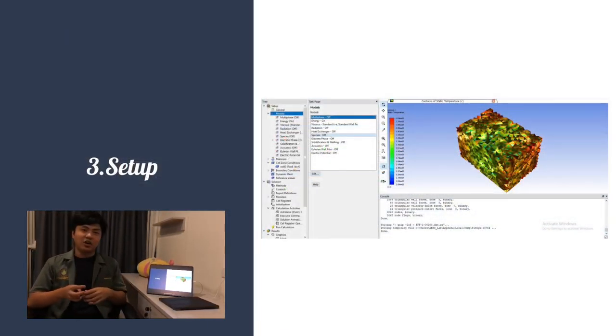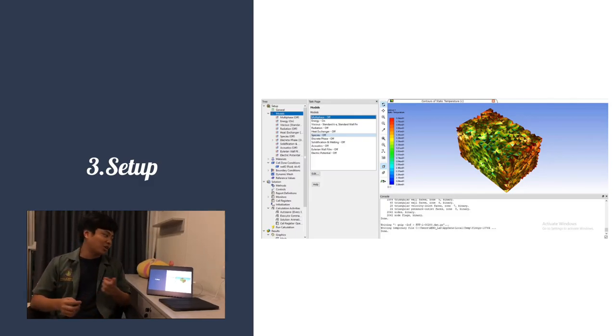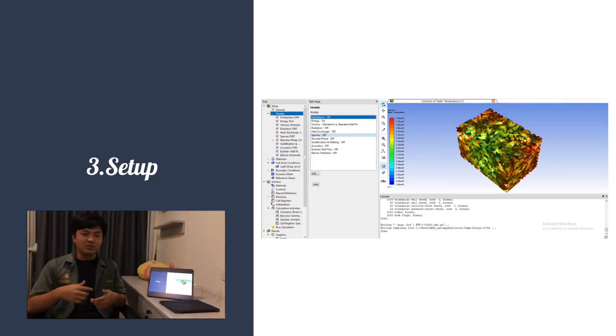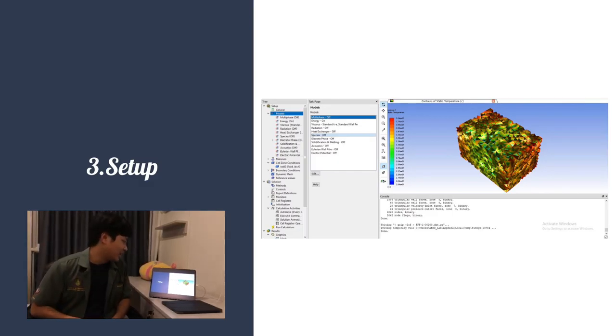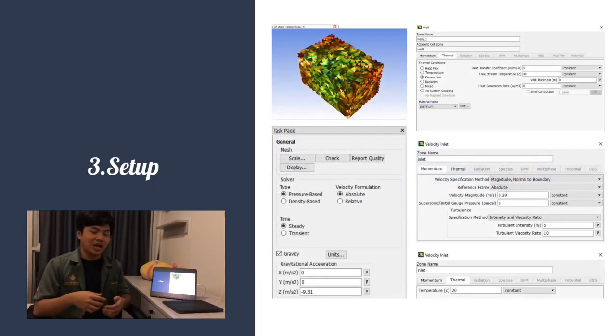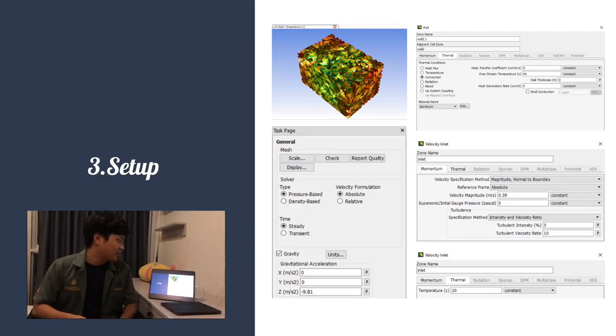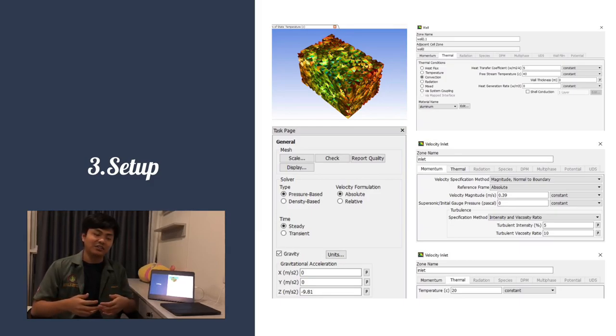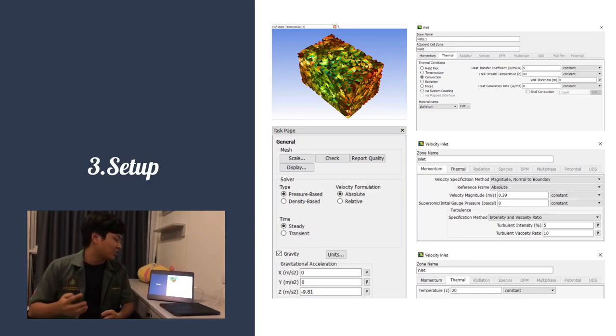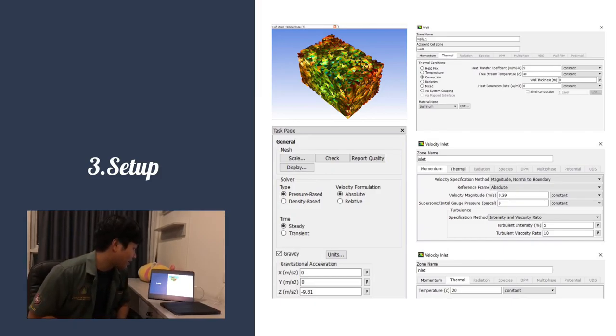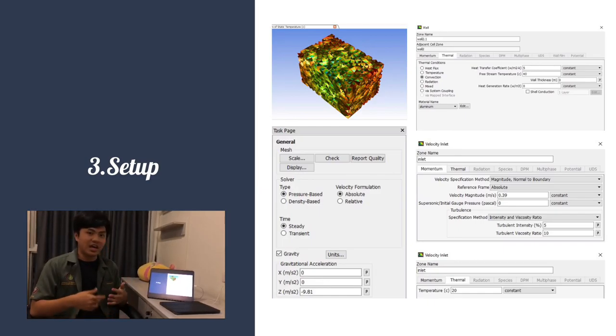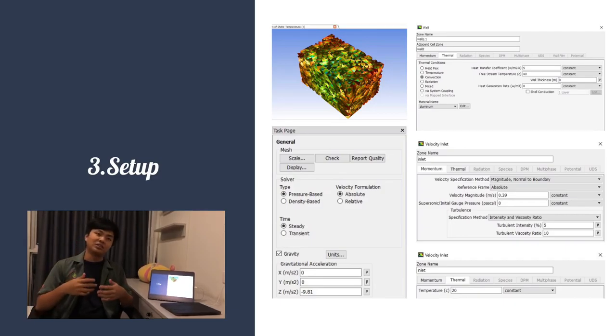For the CFD setup, we enabled the energy equation to observe temperature changes inside the room. We used the viscous standard k-epsilon turbulence model. We also enabled gravity to capture its effect on airflow, and inserted the inlet velocity, inlet temperature, and environment temperature of 40°C. We also set the heat transfer coefficient of the wall to account for outside temperature effects.